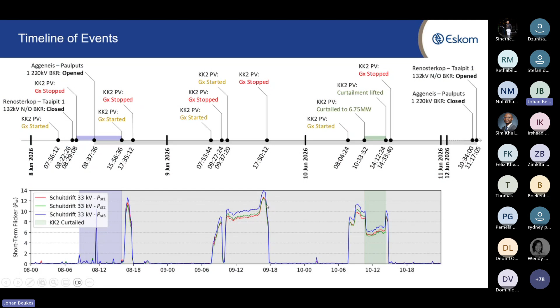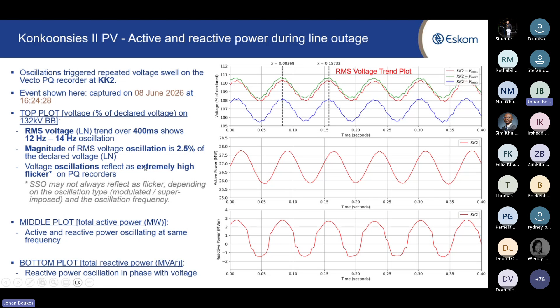A 132 kV line instead of a 220 kV line, and the SCR dropped significantly. It's on the end of that feeder, and suddenly the short circuit ratio at that location dropped to below 3. This is the short-term flicker that we measured during those 2 days, and you can see that the flicker at Schuitdrift substation increased to 15. When the lights flickered, we realized that it was actually one of the 2 solar farms that started to oscillate. So here, we didn't really measure for SSO, but by looking at flicker, we could see there's SSO.